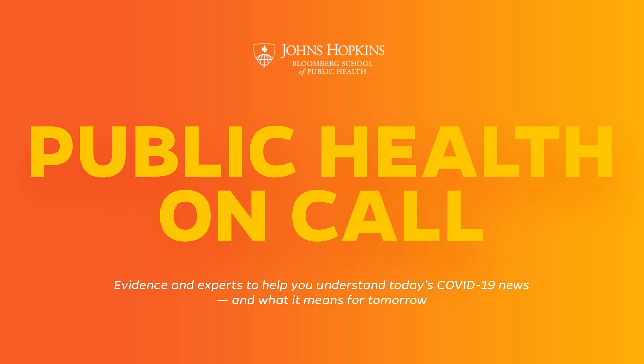That's a big scientific box to check. Exactly. Another big box was to determine exactly how many viral particles the assay was able to detect — something we call analytical sensitivity. We take known genetic material and dilute it down to zero particles, which allows us to determine just how analytically sensitive the assay is. We were happy with the results of the analytical testing. Once analytical testing was done, we took known positive and known negative patient samples as determined by the CDC assay, compared our new test to the CDC test results, completed what we call validation, and then started testing actual patient samples.